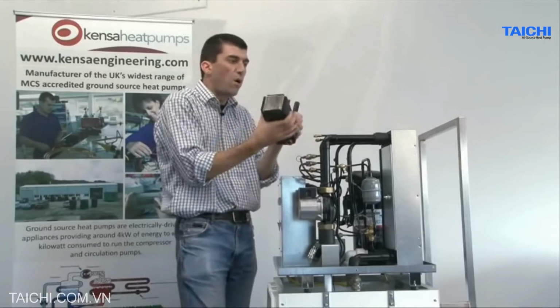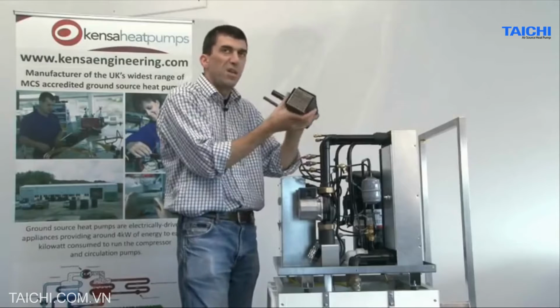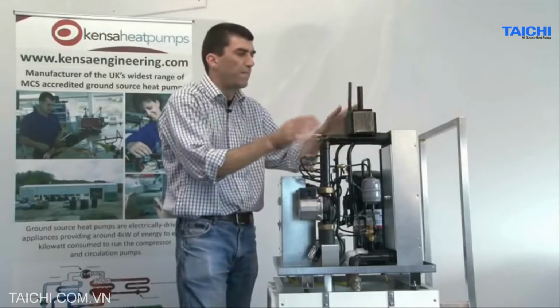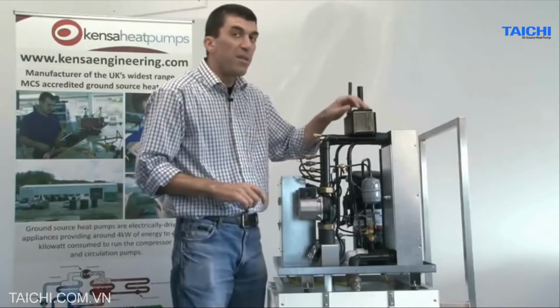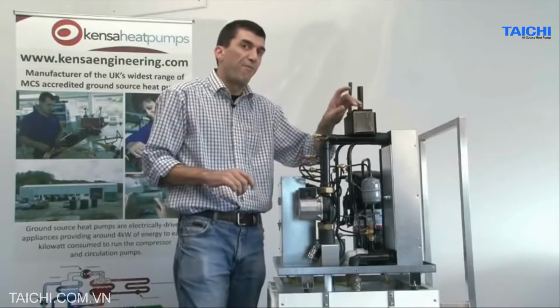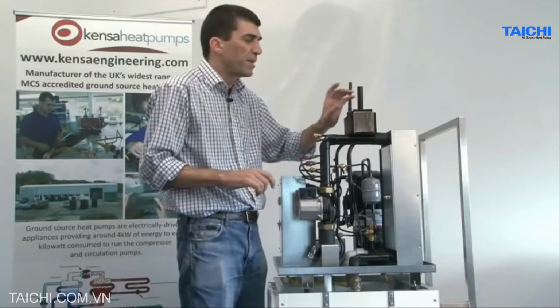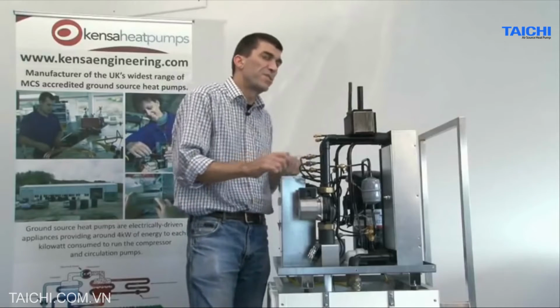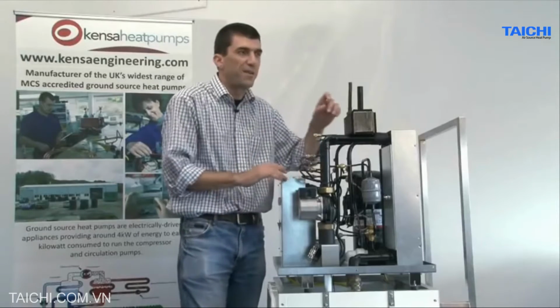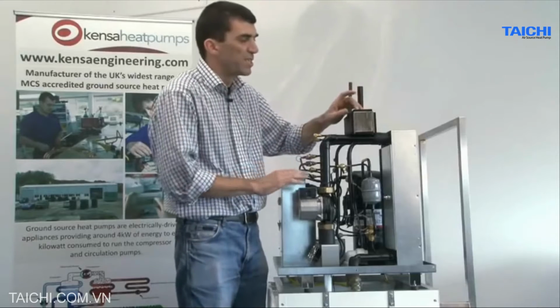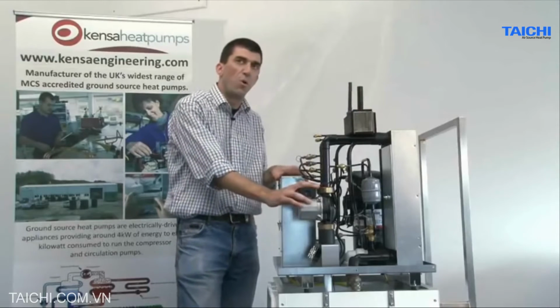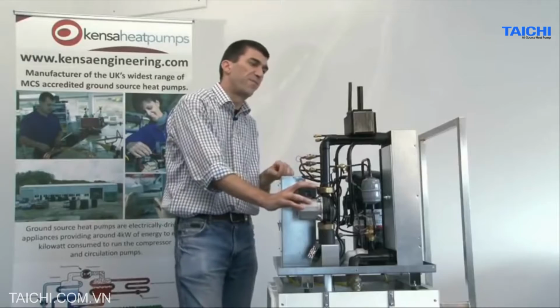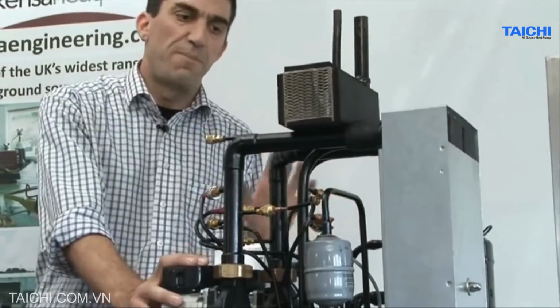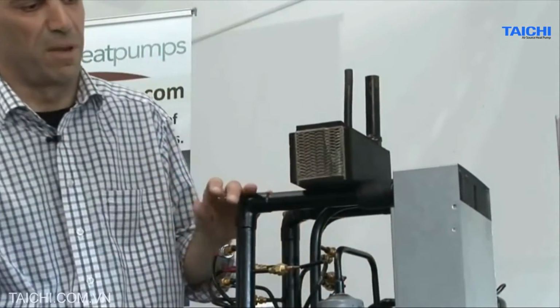These never really go wrong. Because they're usually on sealed circuits, they don't suffer any deposits inside. The only thing that can actually kill them is if they get frozen with fresh water, and that's something as installers you need to take into account on your installations. It may be necessary to put a frost stat on the system if the heat pump is installed in an area where it could be subject to freezing. The other alternative is to put glycol in both water circuits, but you'd need to check compatibility with the underfloor heating system and the other system components.